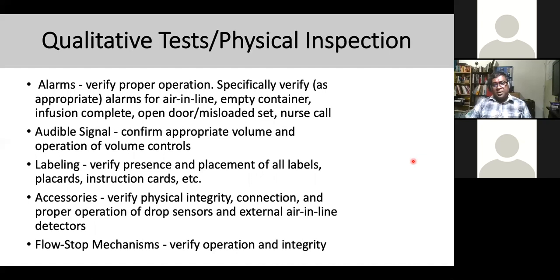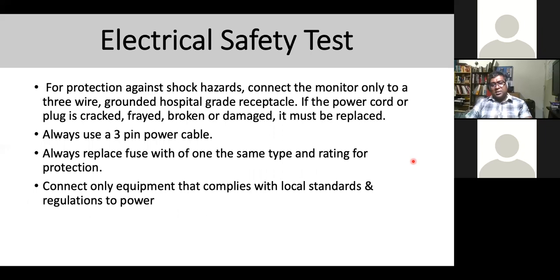Electrical safety tests are one of the important things that you're going to check, against electric shock, like connecting the monitor with only three wires, and make sure there's a ground line, all that. If the power cord plug is cracked, replace it. All these are physical checks actually. And make sure you replace the fuse with the same rating. Do not use a bigger rating or smaller rating. Follow accordingly. And only connect equipment complying with all these standards.